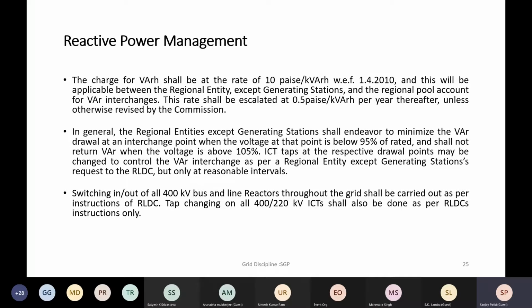Otherwise, especially for hydropower stations which are remotely located and the load centers are much away, producing reactive power and transmitting it over long distances to the load centers becomes non-remunerative and generally not followed. We are again losing the reactive power resource to control the voltage levels in the grid, because the transmission system alone is not able to generate it, because it requires a lot of capital investment. Though it is being done to some extent, that is not sufficient unless the generators also participate in the reactive power management.